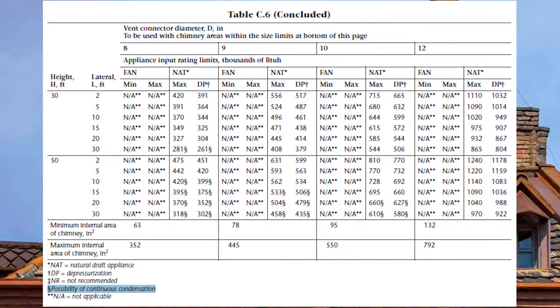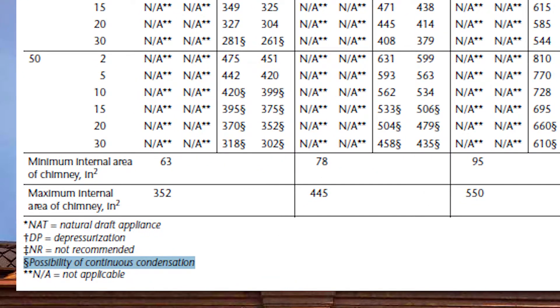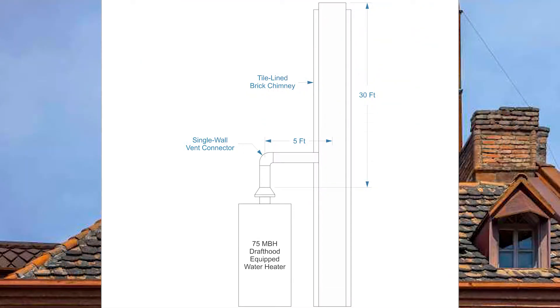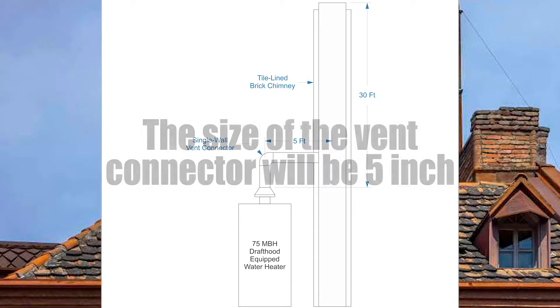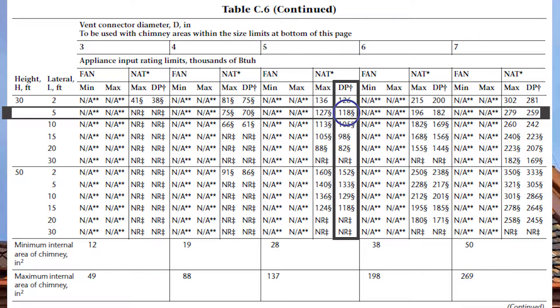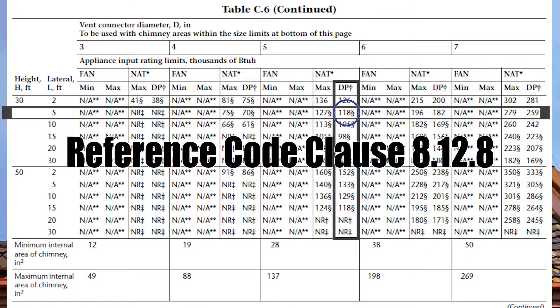We need to look at that symbol. Scroll all the way down to the bottom of table C6 to the legend on the bottom left. This symbol indicates a possibility of continuous condensation, and as discussed in previous videos, condensation in brick chimneys is bad. Regardless, our vent connector size is still 5 inch — this symbol does not mean we can't do this; it's a warning. We definitely need to do a mathematic check from code clause 8.12.8.